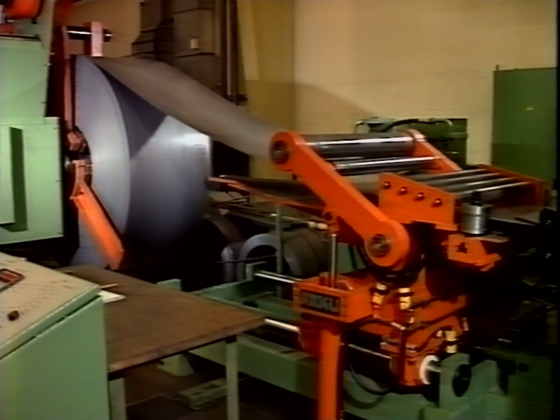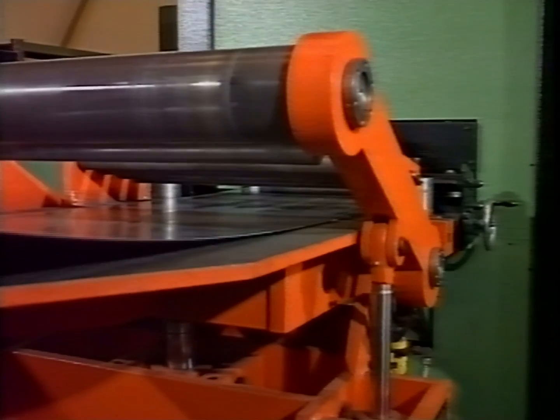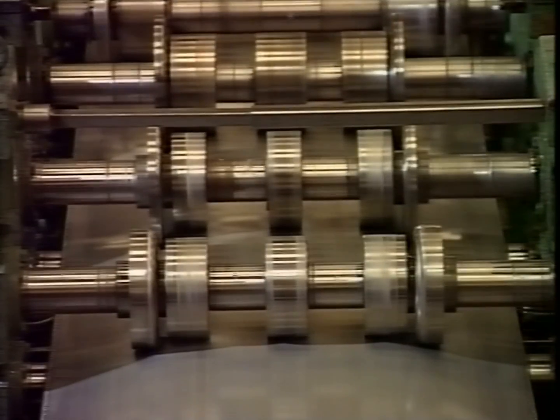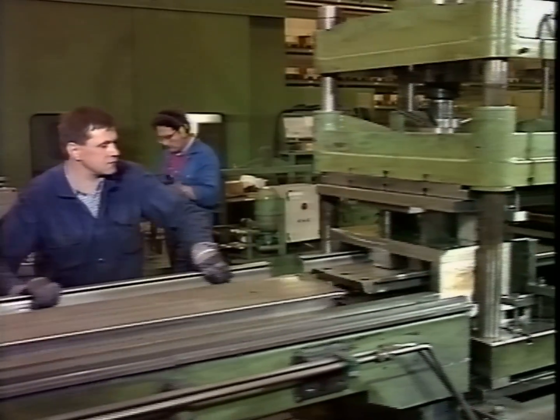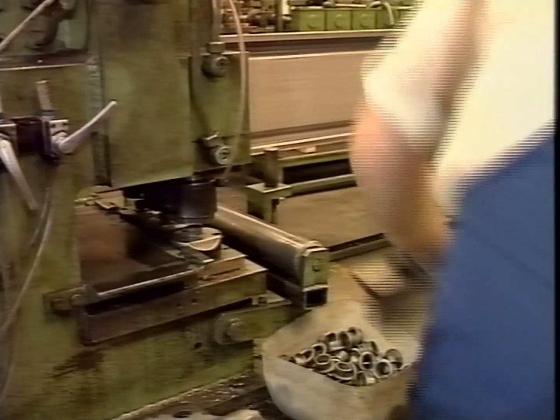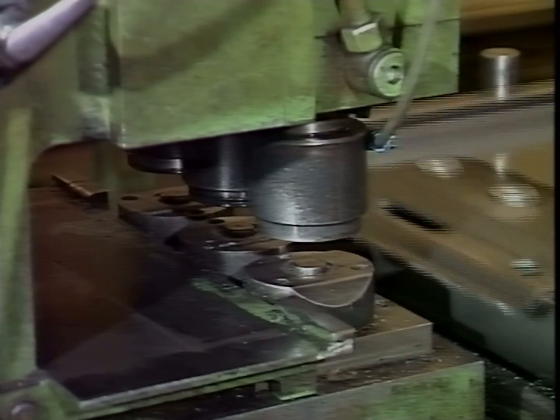The collecting electrodes have excellent vibration characteristics and uniform current density distribution. They are made from double aluminium-killed mild steel. In less than a minute, 24 pairs of rolls form the metal strip into a perfect, torsion-free shape. The resultant high stiffness of the electrodes is a major advantage over other designs. The hanger plate is riveted to the section, which can be up to 15 metres long. Then the finished collecting electrodes are prepared for shipment.